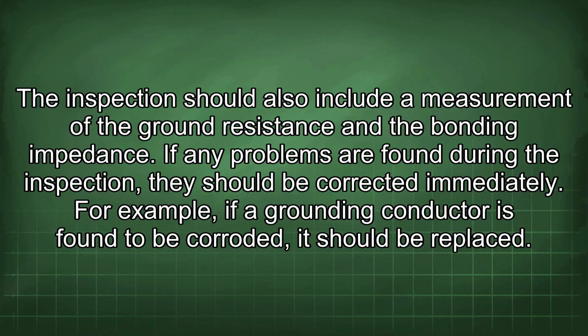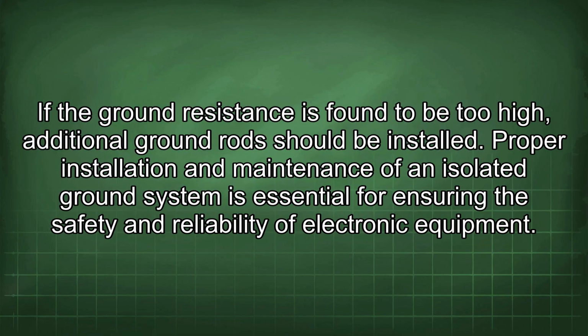For example, if a grounding conductor is found to be corroded, it should be replaced. If the ground resistance is found to be too high, additional ground rods should be installed. Proper installation and maintenance of an isolated ground system is essential for ensuring the safety and reliability of electronic equipment.